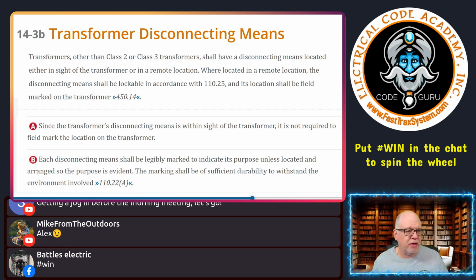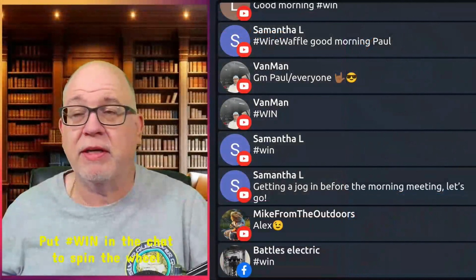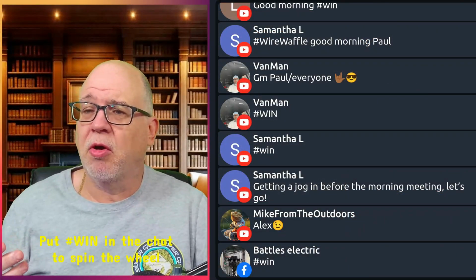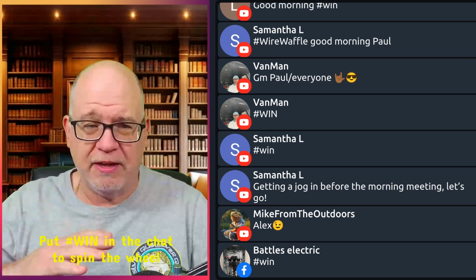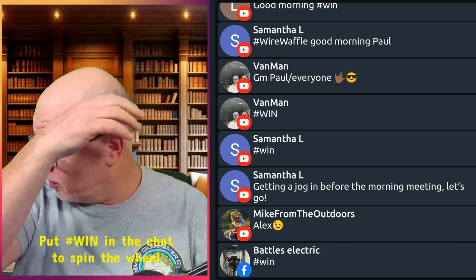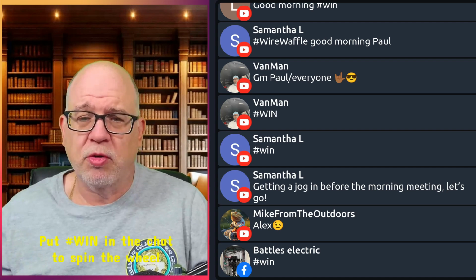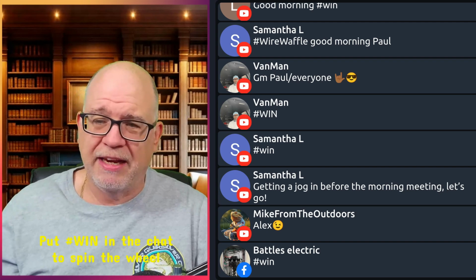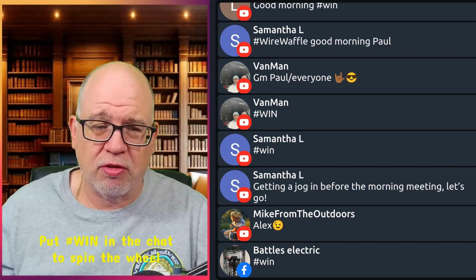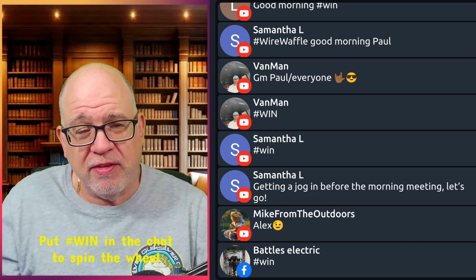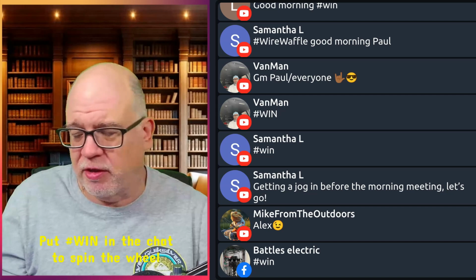Now, I know 99.9% of you probably don't even look at this stuff, and that's why we're going to talk about the disconnecting means, because that's what can vary in the field. As far as protection of the transformer and conductors, y'all probably don't look at that much, probably because the engineers do that for you, right? Unless you're doing an as-built or you're just putting transformers in the field, or adding an additional transformer after the fact, then you probably don't deal with an engineer. But if you do deal with a design professional, they're probably going to already calculate this out. They're going to have looked at the load calcs that are going to be served from that transformer.